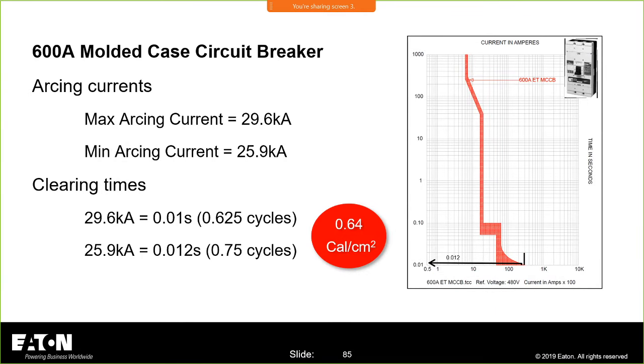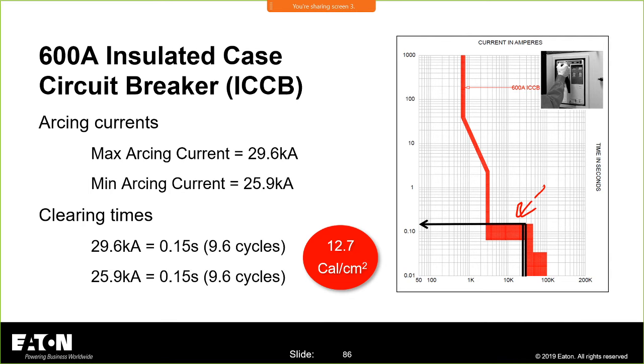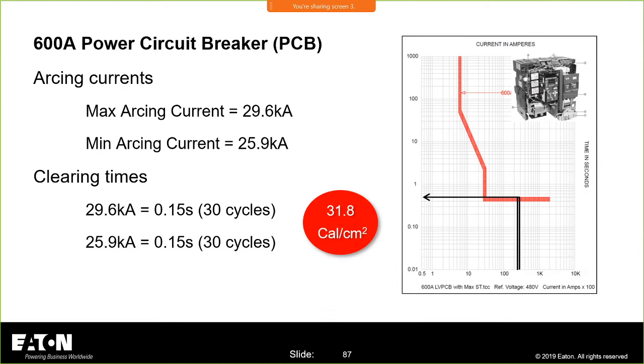So this is just going through the fact, and this is a good example from a clearing time perspective. I've used these slides in other examples. So we know here that for a clearing time of about 0.01 seconds, look, we're in the dirt on this circuit breaker. We're at 0.64 calories per centimeter squared. That's a very light event. But now if I delay that to 9.6 cycles, I moved it up to 12.7. So if I had a circuit breaker that I didn't maintain and it took longer to clear, I could be dressed for point something calories and actually experience double digits. Or worst case, really big double digits.